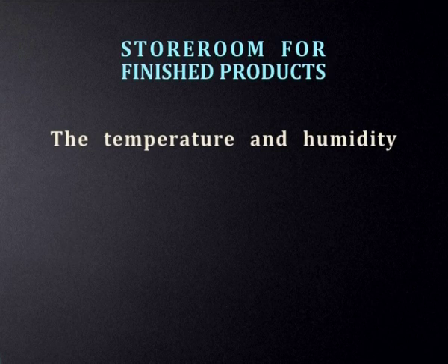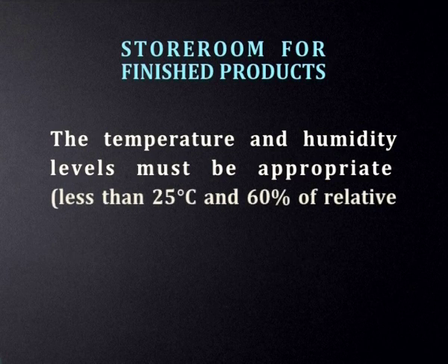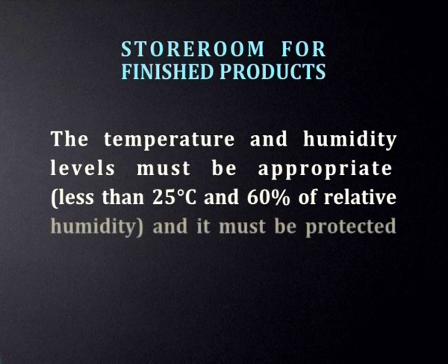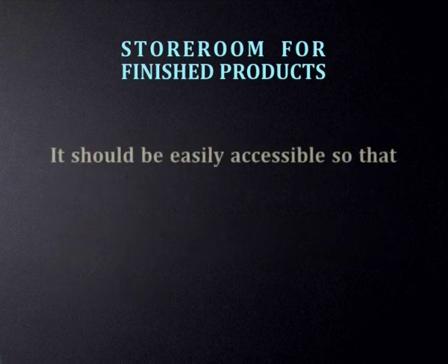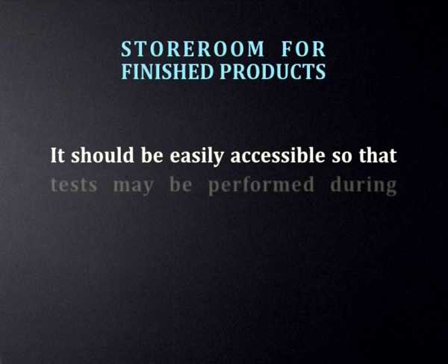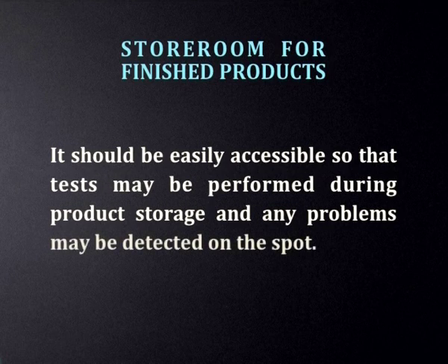The temperature and humidity levels must be appropriate, that is, less than 25 degrees Celsius and 60% relative humidity, and it must be protected from foreign matter and naturally from thieves. It should be easily accessible so that tests may be performed during the product's storage, and any problem may be detected on the spot.